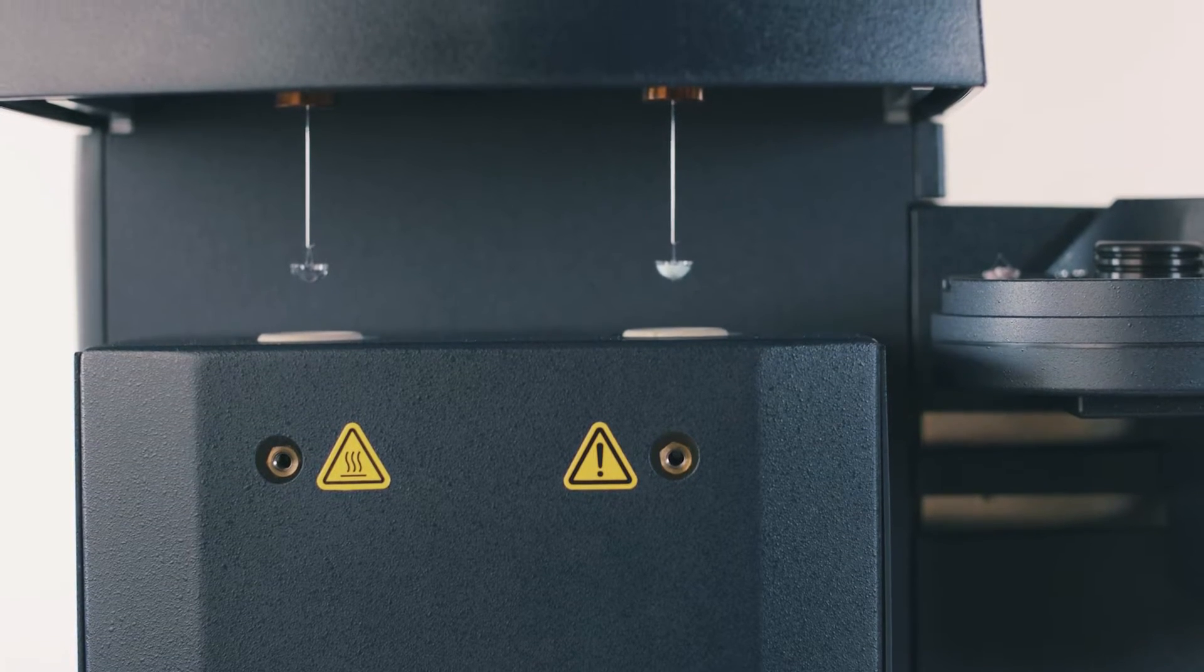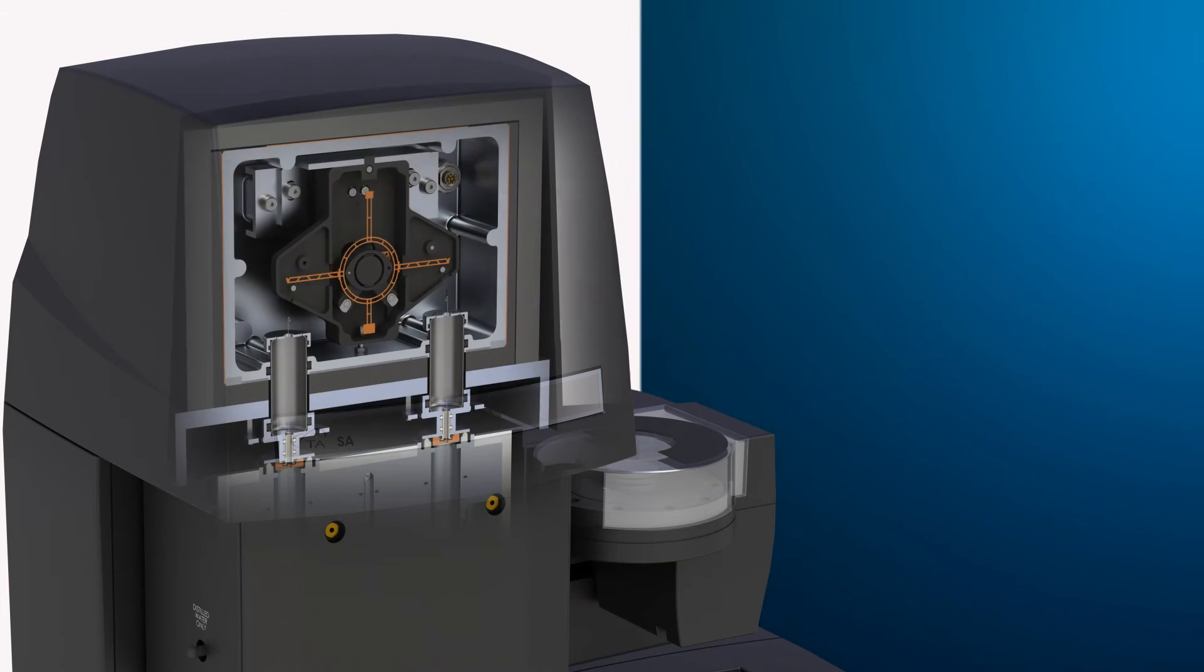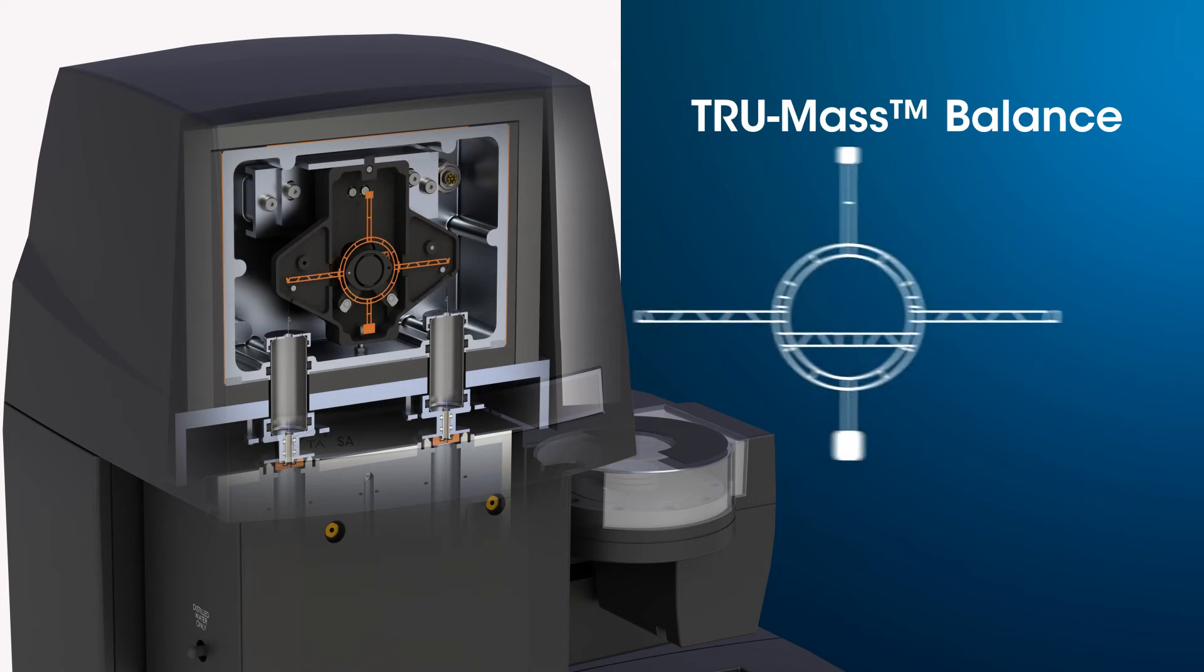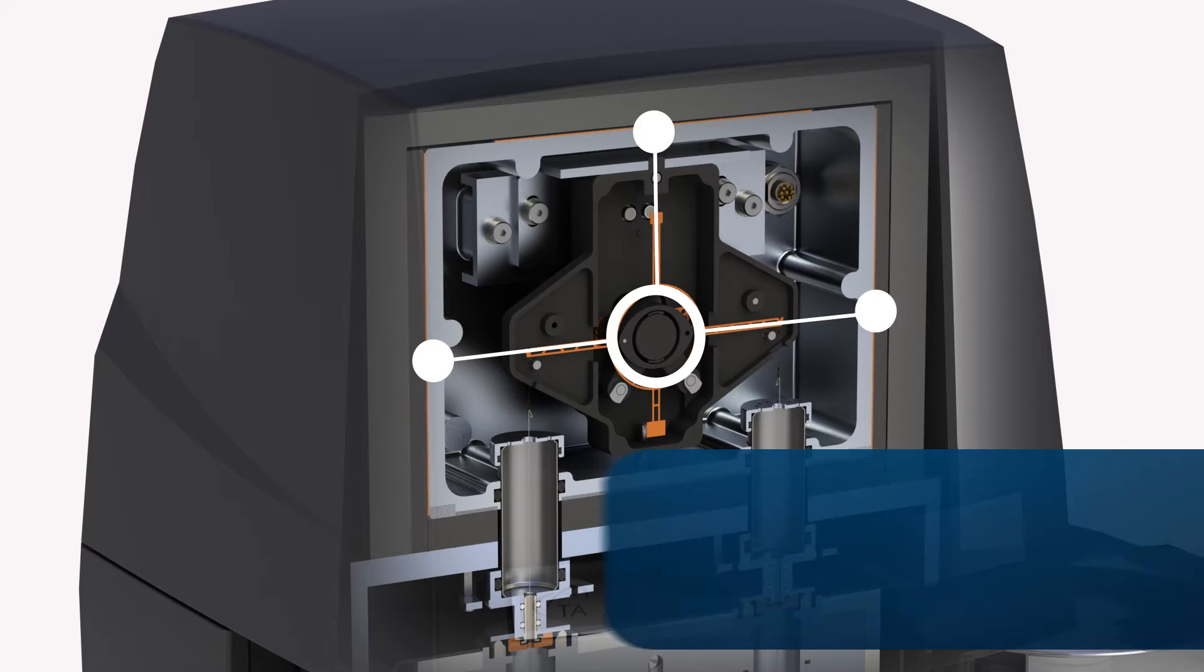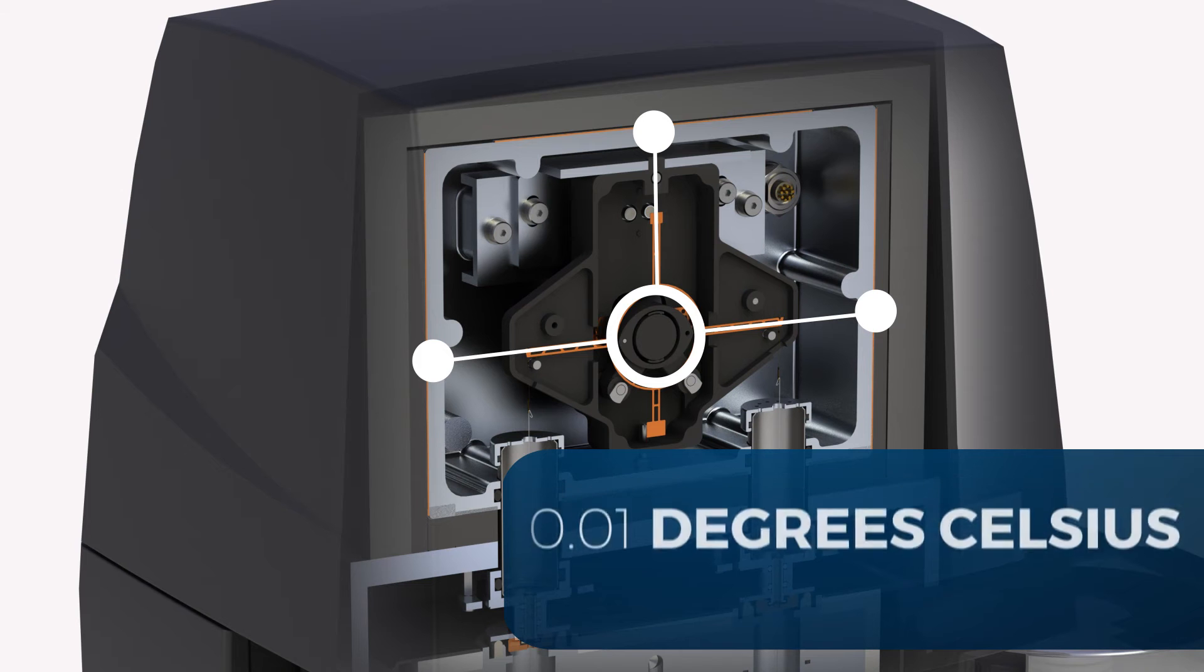Stable, accurate, and precise weight change measurements are guaranteed with the Discovery SA's industry-leading TRU-Mass™ Balance. The ultra-sensitive Null Balance design features three symmetrically arranged heaters that precisely control the temperature inside the balance chamber to within 1/100th of a degree Celsius.